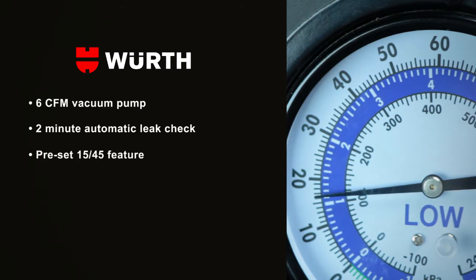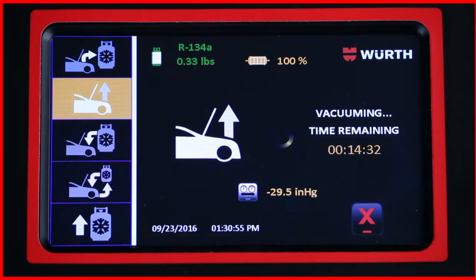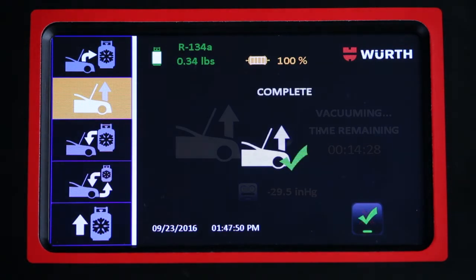A preset 15/45 cycle time allows a 15-minute vacuum followed by a leak test. If the leak test passes, the unit will continue to vacuum for another 45 minutes.